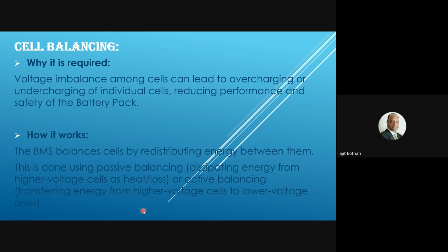Now, why is this important? If any cell has more charge, that will not allow me to charge all cells to 100% level. Let's say that 70% cell, if I don't discharge it, it will only allow my battery bank to charge for the remaining 30% of SOC. But only that cell is getting charged - that 70% cell goes to 100% and stops the charging.